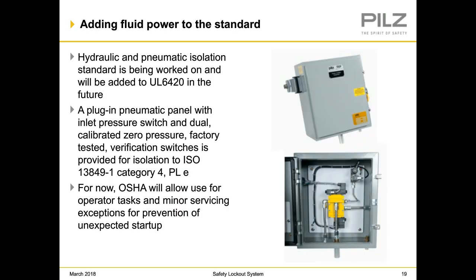Hydraulic and pneumatic isolation standard is being worked on and will be added to UL 6420 in the future. Plug-in pneumatic panel with inlet pressure switch and dual calibrated pressure, zero pressure factory tested verification switches is provided for isolation to ISO 13849-1 Category 4 Performance Level E. For now, OSHA will allow use of these hydraulic or pneumatic panels, I should say, for operator tasks and minor servicing exceptions for the prevention of unexpected startup.